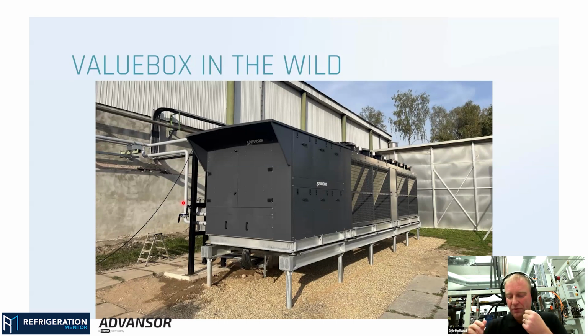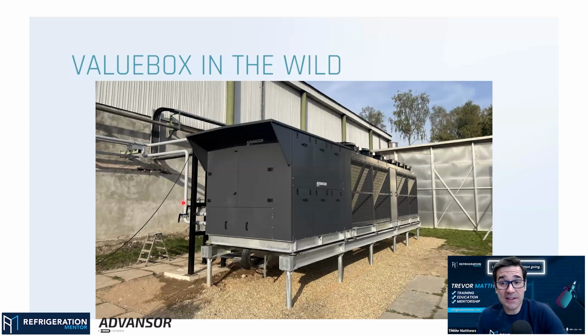And in that case, instead of just generating flash gas for flash gas sake, we can use the ejectors together with this high pressure, high volume gas to lift the liquid from the MT stage to receiver pressure again, again bypassing the compressor. So we're offloading the compressors, so we don't have to strain our compressors as much. We can maybe use fewer compressors on the system. Yeah, and that's what it's all about.